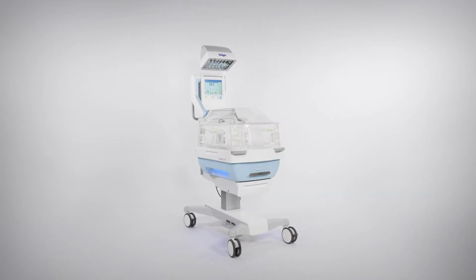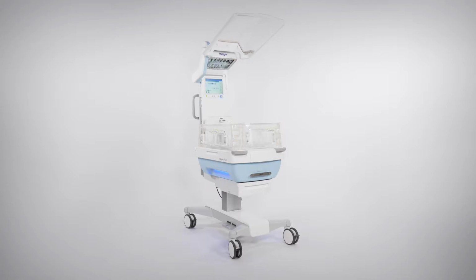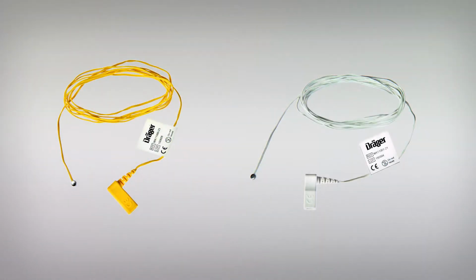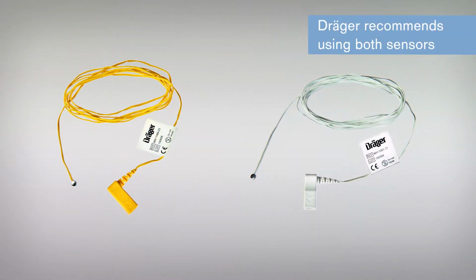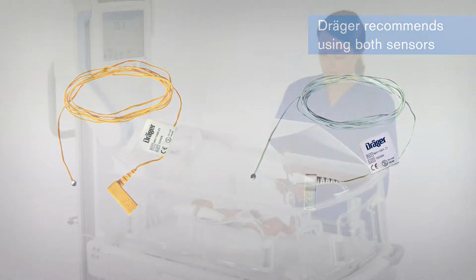Skin temperature mode can be activated in both incubator operation and in radiant warmer operation. The skin mode requires the use of skin temperature sensors. You can operate at minimum with only the central skin sensor connected. However, Draeger recommends using both sensors, the central and the peripheral, for thermomonitoring of the baby.